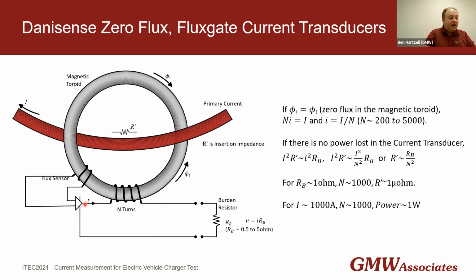In the secondary compensation circuit, the secondary current is measured with a burden resistor, with the voltage output equal to the compensation current times the burden resistance. This burden resistor can either be integrated in the transducer measurement head, or you can take the current signal all the way back to your measurement instrument and use the burden resistor at the instrument to get the voltage measurement there instead.